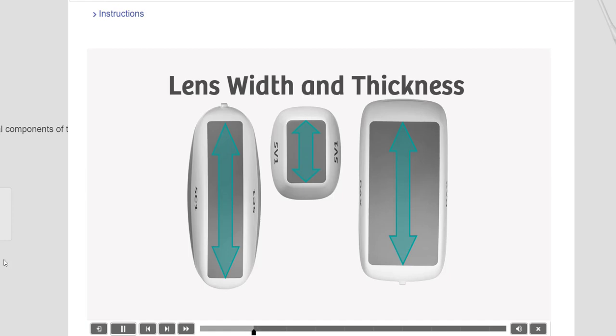The orange arrows stretch across the elevation. The lens has a focusing effect in the elevational direction. The elevation affects the slice thickness of the beam. As seen in the diagram, this lens is an external component. In some transducers, the designs also include lenses within the transducer.